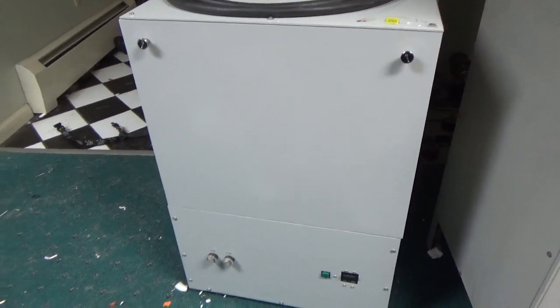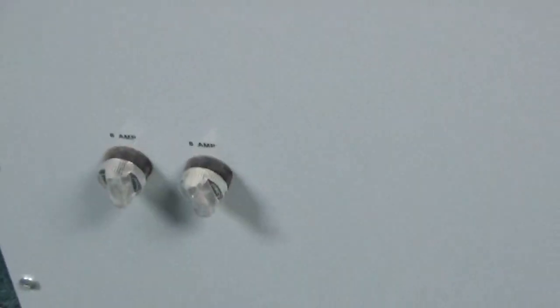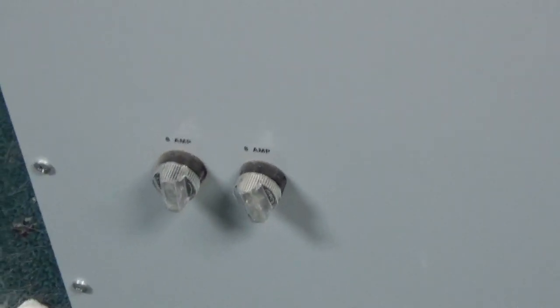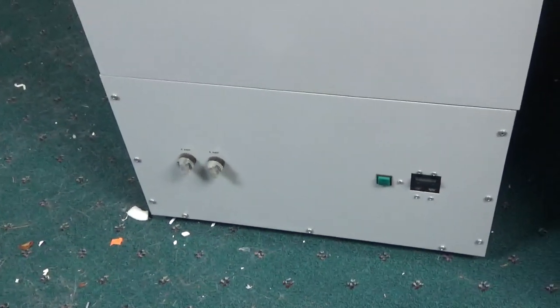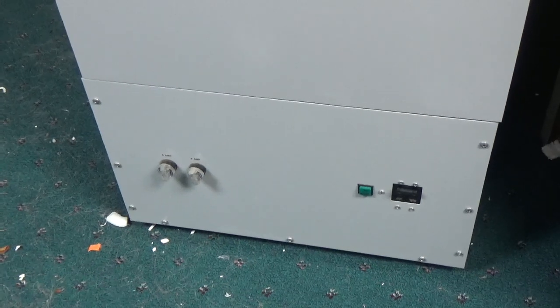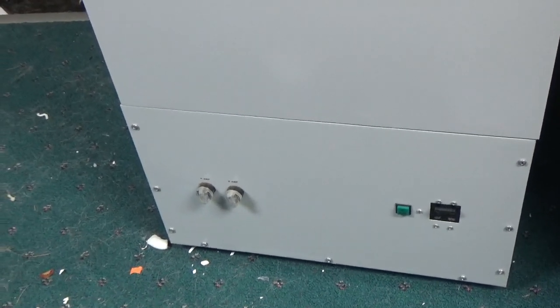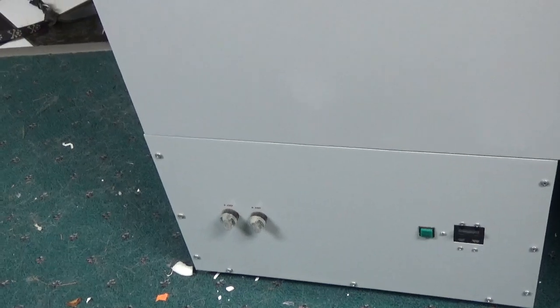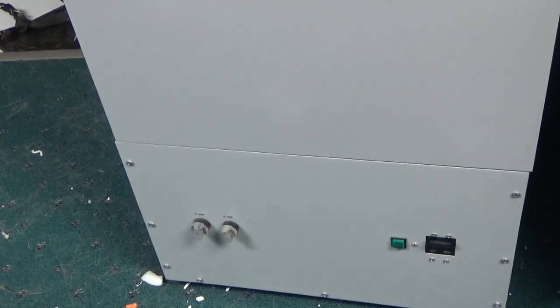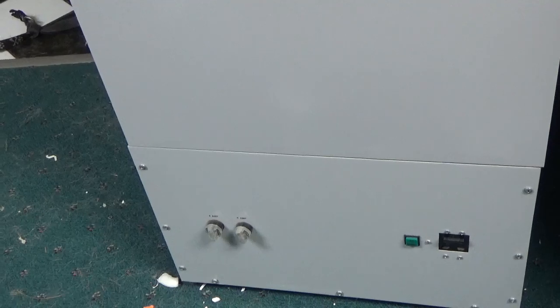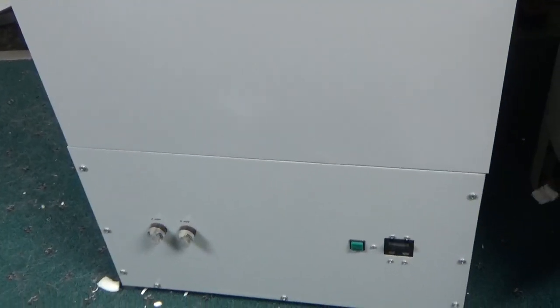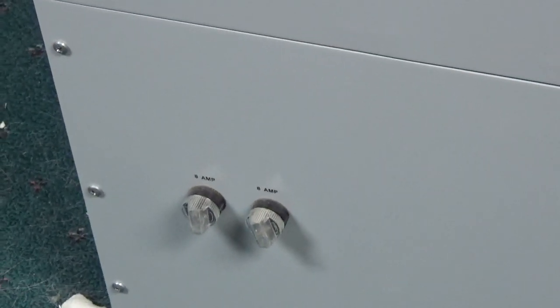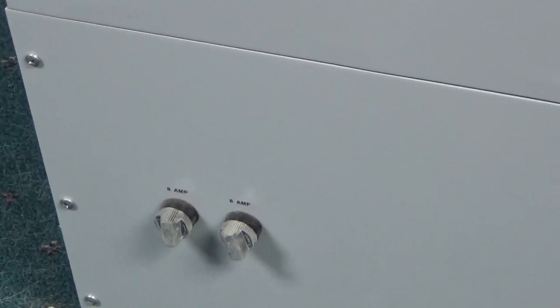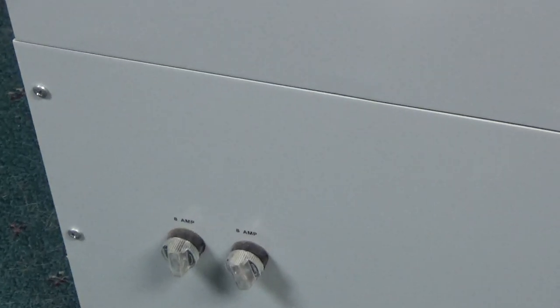In the later version ones, they actually added a third fuse holder, so if that supply failed, it would pop the line fuse instead, and it wouldn't be a fire hazard or melt down the transformer. I can show you a picture - I don't think I have the transformer here, but I can show a picture the customer sent me. I have that same fuse holder, and if I think I can get it going, I'll add it. But it just boils down to how much time it's going to take.